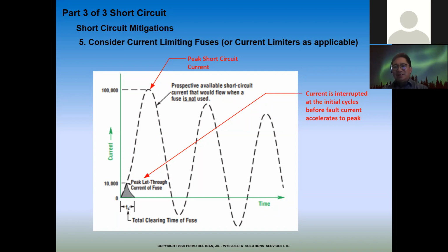Let's face it, it depends on how many things are connected to our system at the time of the fault - that determines how many motors or sources contribute to it. So that's how they used to do it. I think they're still doing it now for extra high capacity, like if you need more than 100 kA - we call this a series rated system or cascaded system.